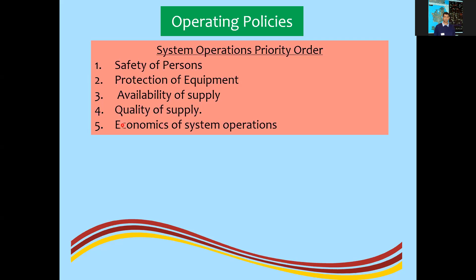You already know that active power, megawatts, is connected to frequency, and how that happens via stored kinetic energy. Similarly, system voltage is connected to reactive power. So sometimes we have to use generators to supply reactive power, even in violation of the merit order—but that is allowed because economics comes at the bottom.